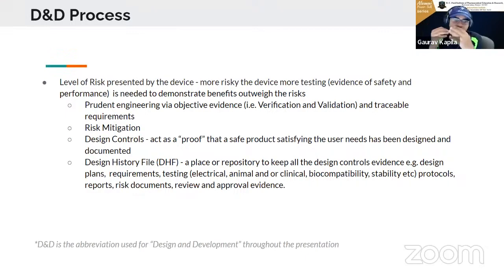It has more components. It has more interfaces, external and internal environments. The level of risk is different. So it all depends on the level of risk that is posed by the device and the intended use. Now, we deploy risk mitigation throughout the product development, which means we need to study the risks. As soon as you have an idea that you are going to start working on the project, you have a proof of concept, you do an early hazard analysis or risk analysis to see what kind of risks this product can have in the field, what kind of risks the product can have when the operators use it, those are called the usability risks, and what could be the risks to the end users.